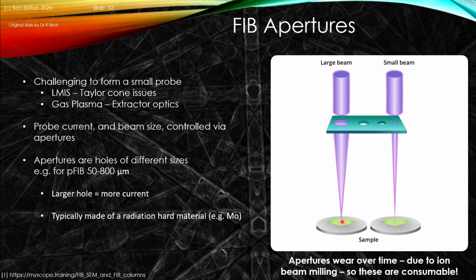Now, why is this important to note? Well, these apertures, this incident beam, will hit the aperture and can wear this aperture over time. So, due to ion beam milling of the aperture strip, the apertures themselves are actually consumables in a FIB-SEM instrument. And that's super important to bear in mind because, for instance, the current for a particular aperture, if the instrument is not well maintained, might drift over time.